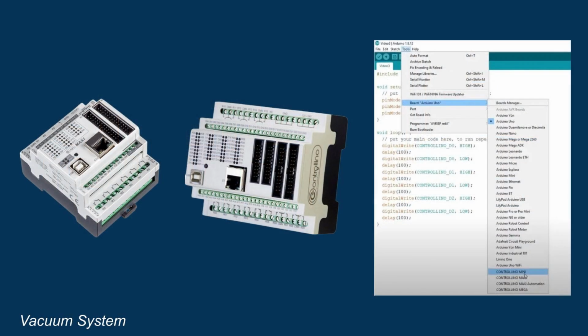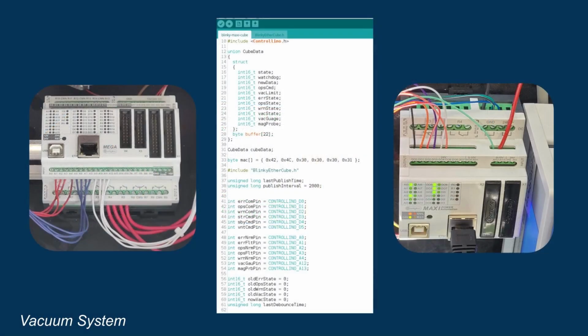For the necessary ruggedness, Blinky-Lite uses the Controllino, an open-source PLC. The Controllino offers rugged housing, relays, 24-volt digital and analog I/O, yet it can be programmed with the open-source Arduino IDE. This open-source choice allows us to easily control the vacuum system with other open-source PLCs and, more importantly, version the code for documentation. We developed an interface between the Blinky-Lite control system and the Controllino by simply providing a straightforward map between the database and the PLC controls.